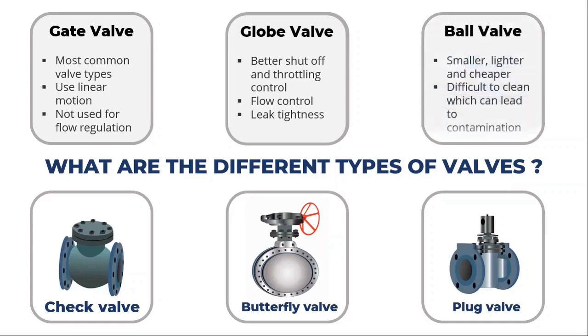A hollow ball is used by a ball valve to start or stop fluid flow. The valve handle can be used to pivot the perforated ball — the fluid flows through when the ball's hole is pointed at the flow entrance. When compared to gate valves of the same size and rating, ball valves are more compact, lighter, and less expensive.